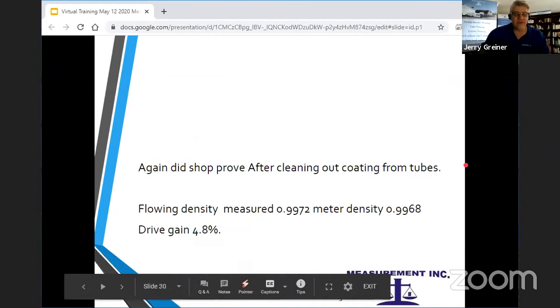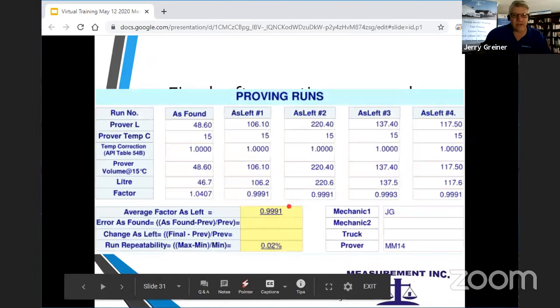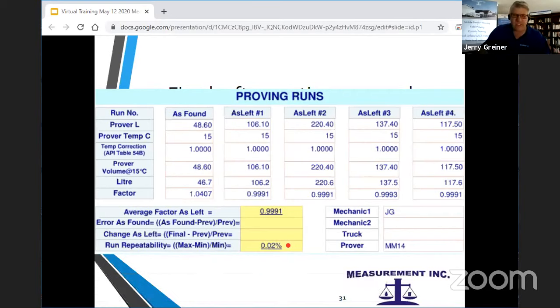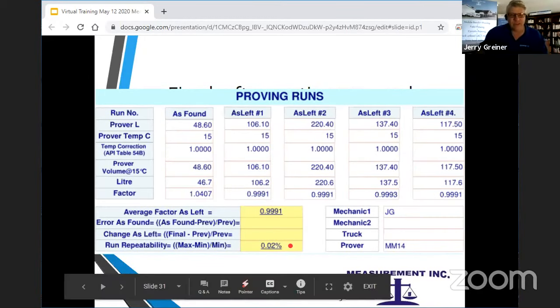We again did a prove right after cleaning, and we found the density lined up just about exactly with what it really was. Drive gain was 4.8%. And so we did some proves. The meter factor was 0.9991, and there was 0.02% between runs, where before it was like 6 or 7%. As soon as we were done, it had just 0.02% between runs. Basically, it worked perfectly like it should.